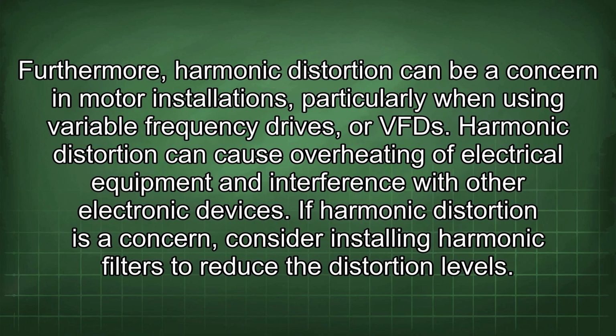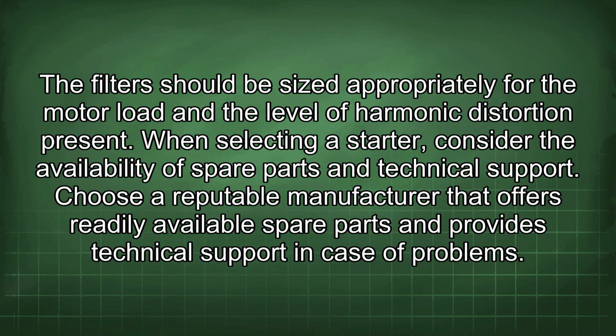Furthermore, harmonic distortion can be a concern in motor installations, particularly when using variable frequency drives, or VFDs. Harmonic distortion can cause overheating of electrical equipment and interference with other electronic devices. If harmonic distortion is a concern, consider installing harmonic filters to reduce the distortion levels. The filters should be sized appropriately for the motor load and the level of harmonic distortion present.